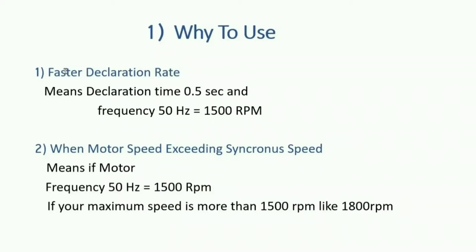First, in faster deceleration rate — if the deceleration rate is set at 0.5 or less and the frequency is 1500 or more, then when we stop the motor the voltage exceeds. Second, when the motor speed is exceeding synchronous speed — that means above 1500 RPM normal motor speed — if it is running at 1800 or more, then there will be an overvoltage.